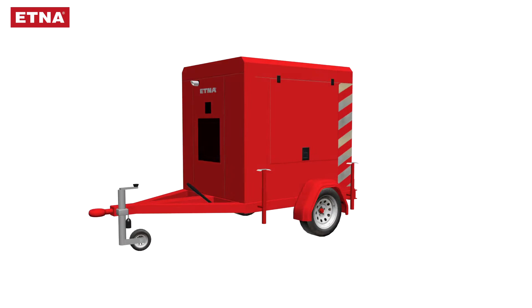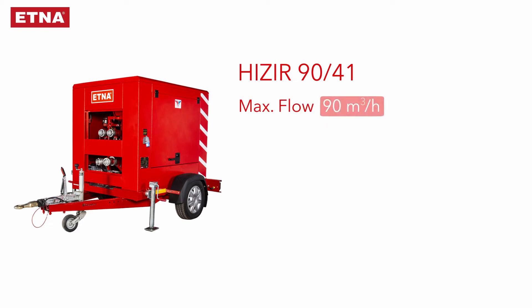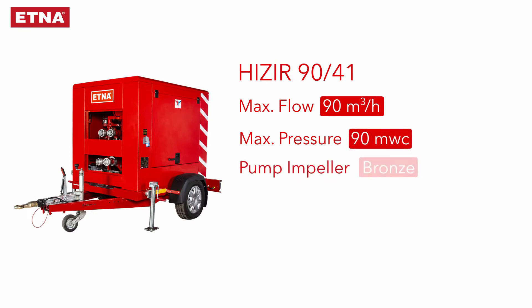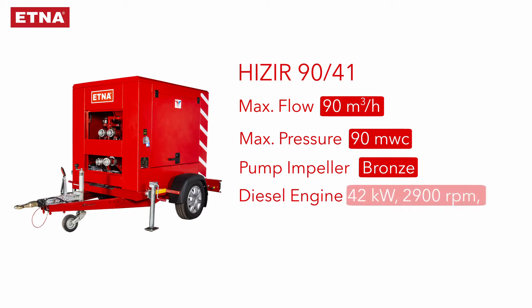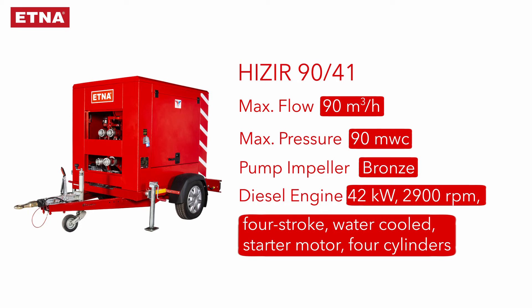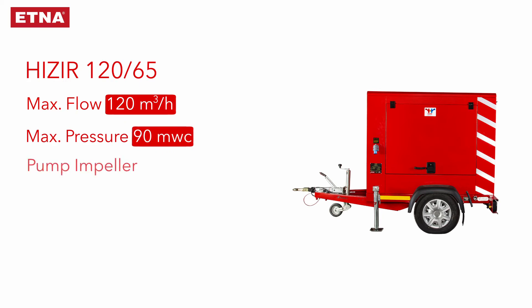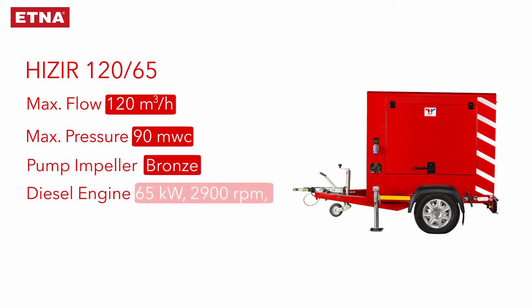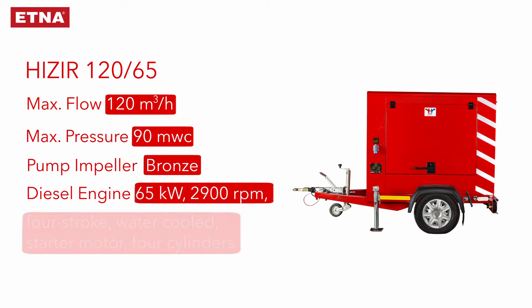Hizir is produced in two capacities. The Hizir 90/41 has a maximum flow of 90 cubic meters per hour, maximum pressure of 90 meters of water column, a bronze pump impeller, and a diesel engine: 42 kilowatt, 2900 RPM, four-stroke, water-cooled, with starter motor and 4 cylinders.